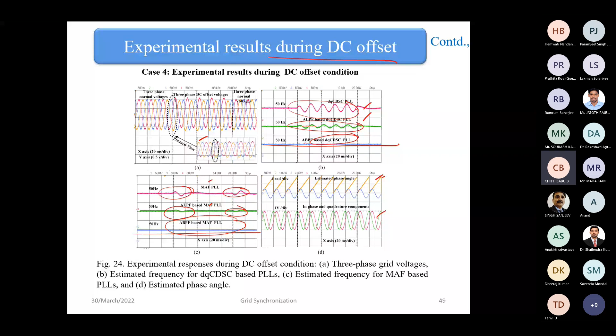It is able to track the fundamental phase angle very accurately, and also generate the sine theta and cosine theta components very meticulously. Moreover, these two components must be orthogonal to each other, so that we have the possibility of independent control of active and reactive power, which is essential for independently controlling the utility grid voltage and frequency.